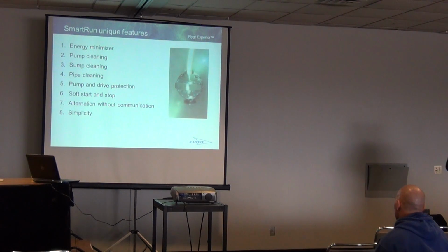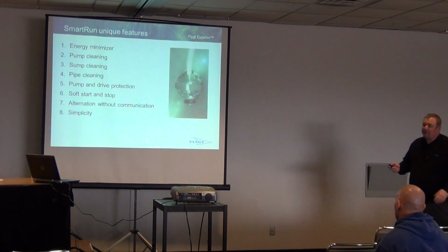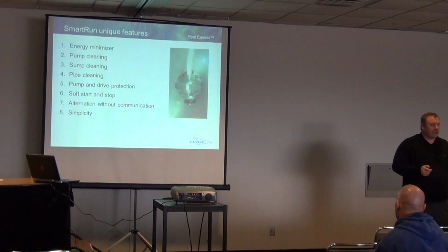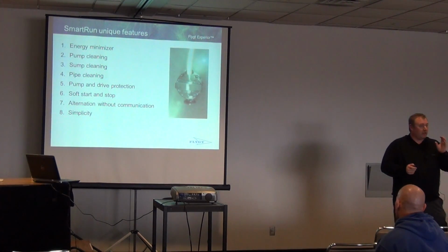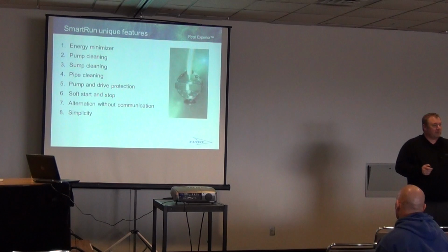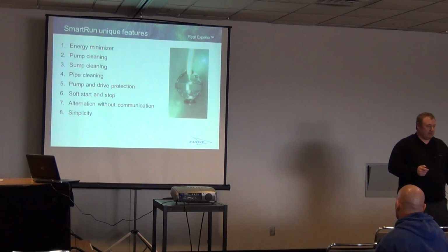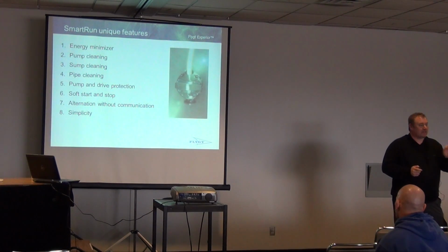Pipe cleaning, it's got pipe cleaning functionality. So really, what does this unit do? In the scheme of things, what we're doing is we're taking your pump, we're picking a selection in our pump line, and we're optimizing the speed of that unit to the best efficiency point on the curve of that pump to maximize its best efficiency point in your system.